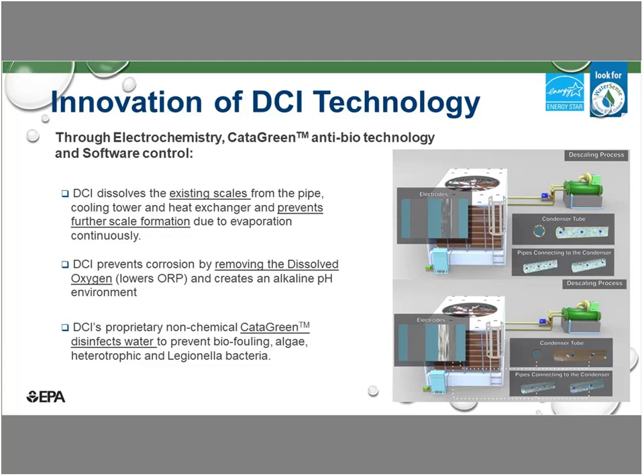Okay. What happens is that, using electrochemistry, we plate the scaling minerals onto our electrodes. So when we take the minerals out from the water that passes through our system, we deposit the scale in our system. The water going back out to the cooling tower is then very low in scaling minerals, and because it's very low in scaling minerals, it wants to dissolve scale that is already in the system, right?